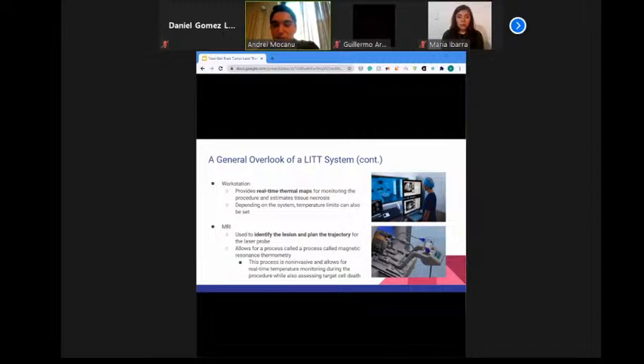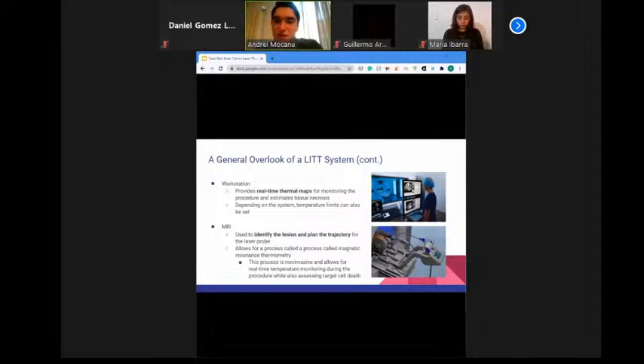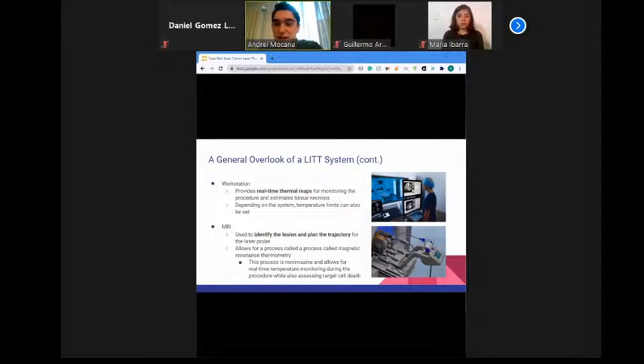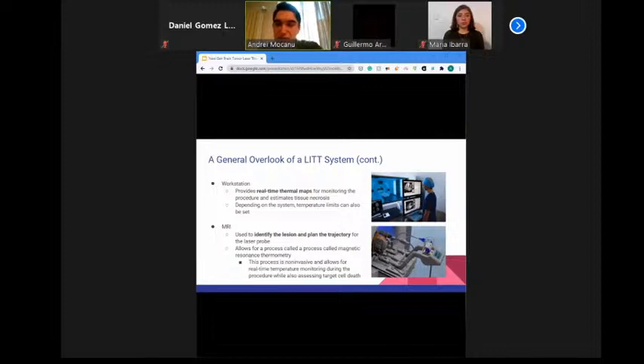The laser shuts off automatically if the valid temperature range at the tip is exceeded. The MRI is essential to the safety of this procedure. Successful thermal ablation requires accurate targeting of the tumor and maintenance of sufficient temperature while excluding damage to surrounding tissue. MRI is used to identify the lesion, plan the trajectory for the laser probe, and visualize and quantify heat deposition — a process called magnetic resonance thermometry.